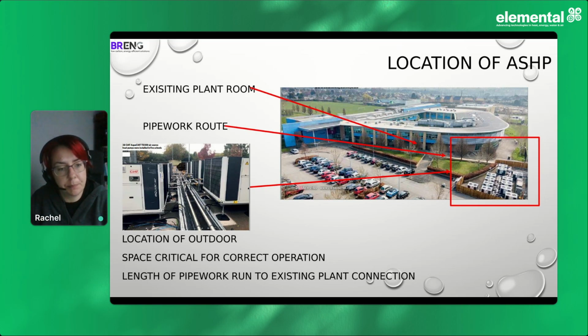What doesn't help is every air conditioning unit and air-to-water heat pump is always published at a certain condition of 7 degrees ambient. So when everybody looks in the book and says, well, I've got 80 kilowatts of air source heat pump, that's at 7 degrees, which isn't this climate. We size at minus 5, and at minus 5 that 80 kilowatts becomes about 50. Some people pick an 80 kilowatt unit thinking, 80 kilowatt boiler, I'll get the 80 kilowatt heat pump, in it goes, and they wonder why it struggles and can't get to temperature. It's because not enough thought's gone in at the beginning about what do I actually need.